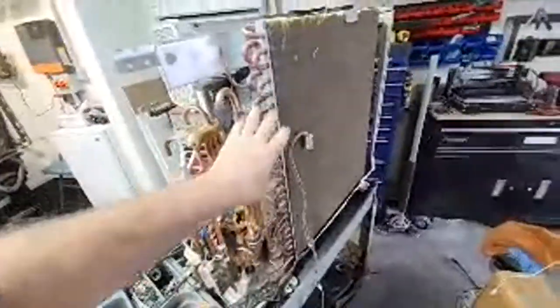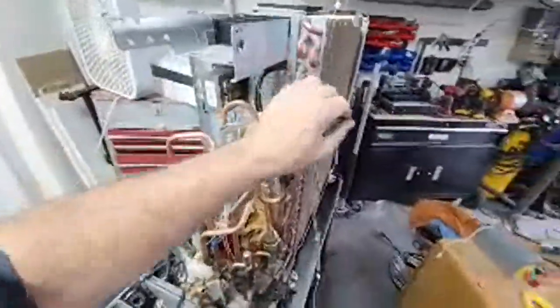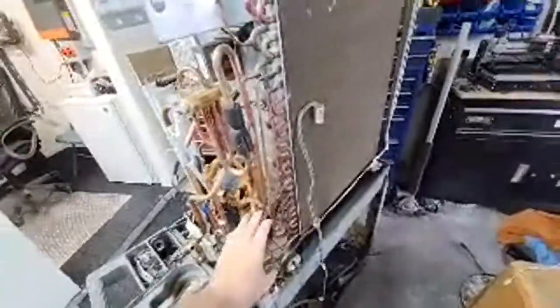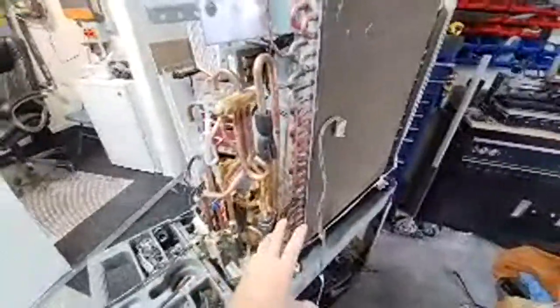So I'm going to split this into 2 circuits, and then this will be an evaporator. So in the winter, it'll be like the normal heat pump, like it is now outside for the water heater, just taking the heat from the outside air. And then I'm going to take this bottom section, and I'm going to make it into a condenser. And what I'm going to do is a series condenser. It's going to go through the water heat exchanger, and then it's going to pass through this coil.